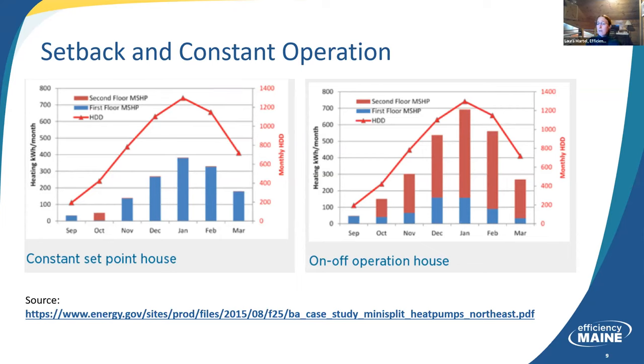And the reason why I wouldn't recommend it is because of the results that I'm showing here, as well as some results that I'll show in some of my later slides. So this is exactly the same configuration of a home run in two different ways. There are two heat pumps in this home. The red one's on the second floor, the blue one's on the first floor. And the line there is the heating degree days. So in the configuration on the left, they picked a comfortable temperature and set it and left it. They did not adjust the thermostat in that home. You'll see that the first floor heat pump carried almost all of the load of the home. It was able to satisfy the indoor temperature request through all months with very little second floor heat pump use.